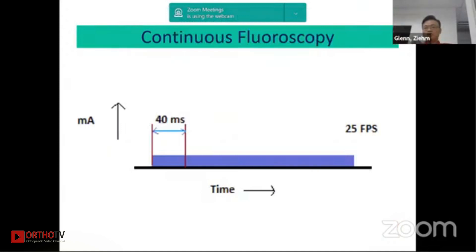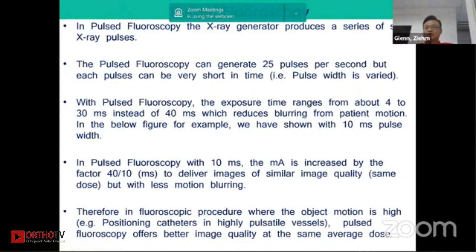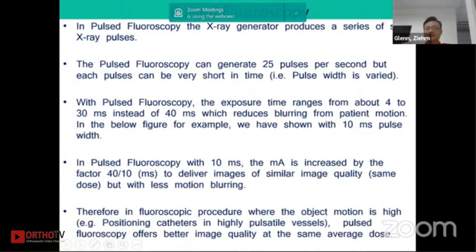In pulse fluoroscopy, the x-ray generator produces a series of short x-ray pulses. Pulse fluoroscopy can generate 25 pulses per second, but each pulse can be very short in time. With pulse fluoroscopy, exposure time ranges from 4 to 30 milliseconds instead of 40 milliseconds in continuous fluoroscopy, which in turn reduces blurring if the patient moves.